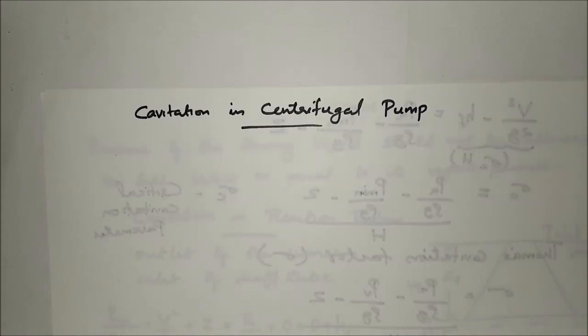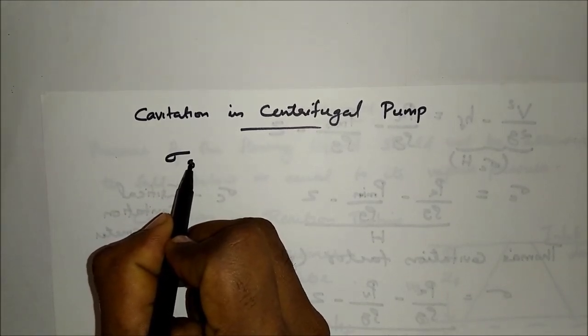Cavitation in centrifugal pumps: in the case of centrifugal pumps, cavitation may occur at the inlet of the impeller or at the suction side of the pump, where the pressure is considerably low. Due to cavitation there will be a sudden drop in efficiency and head. In order to determine whether cavitation will occur in any portion of the suction side of the pump, the critical value of the Thoma cavitation factor is calculated.